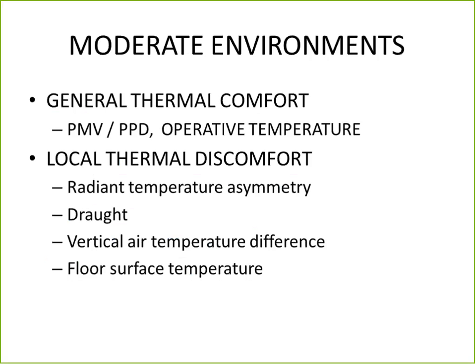When we talk about the thermal environment, we have kind of two approaches. If we have buildings with mechanical heating and cooling systems, we use as a criteria for the thermal environment an index for thermal environment, PMV, PPD, or the criteria could also be expressed as a range of operative temperature.